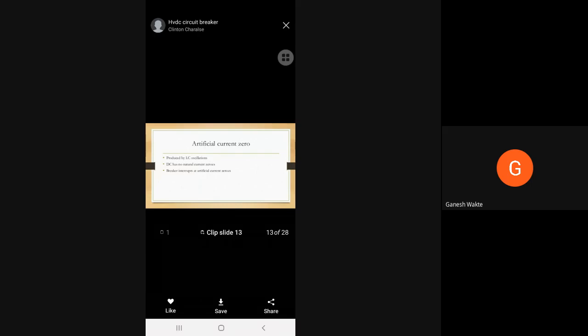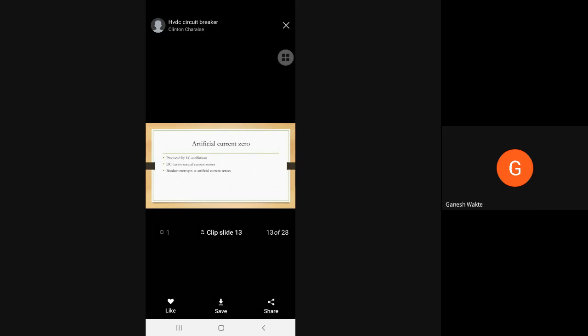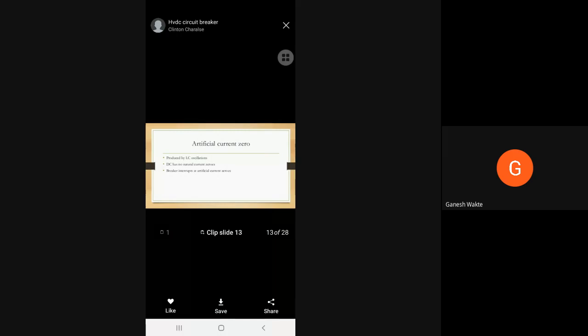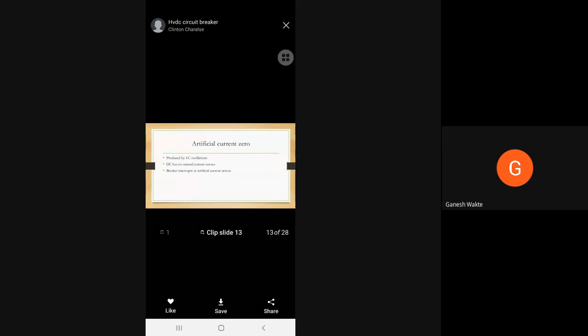Artificial current zero. Natural current zero, which is not available in DC because the magnitude of the DC is constant. But what happens in AC? We see that it starts from zero, then the magnitude increases. So you can say in AC alternating quantities, there is a natural current zero. Therefore, current quenching is easy in AC as compared to DC. Therefore, we have to create here artificial current zero. That is very difficult.